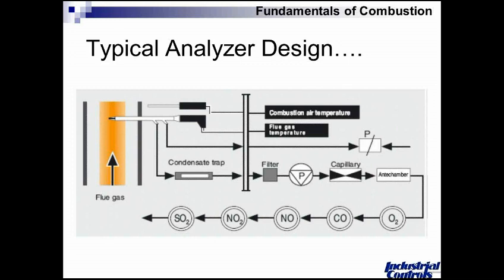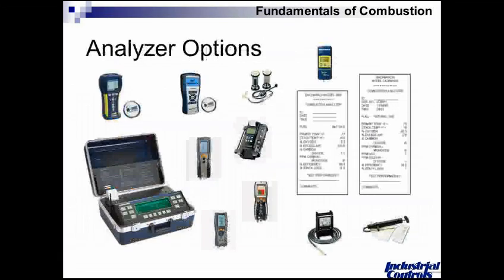There's emissions analyzers that have many cells for measuring other gases of interest. We look at our combustion air temperature and our ambient. We get our net temperature difference, and between net temperature and oxygen content, that's predominantly what's used to calculate the efficiency.